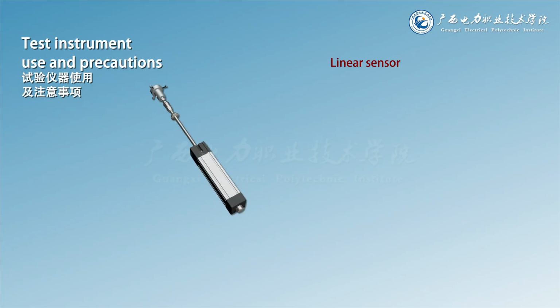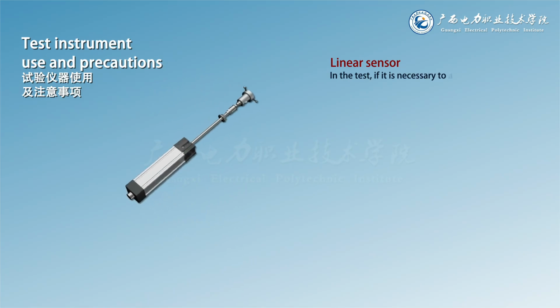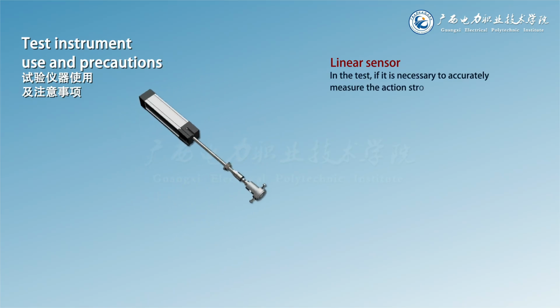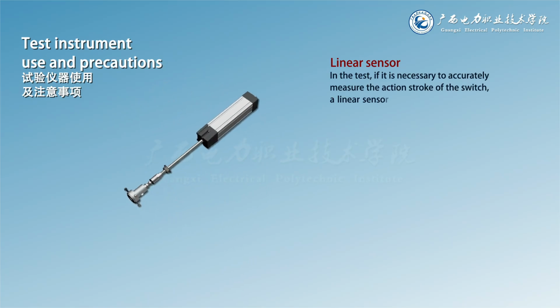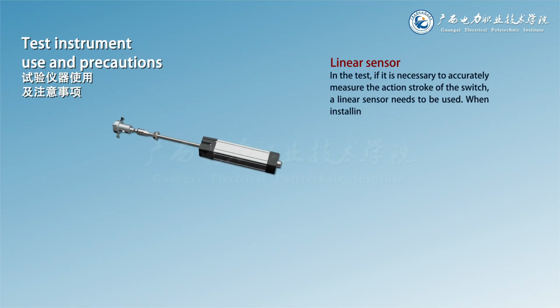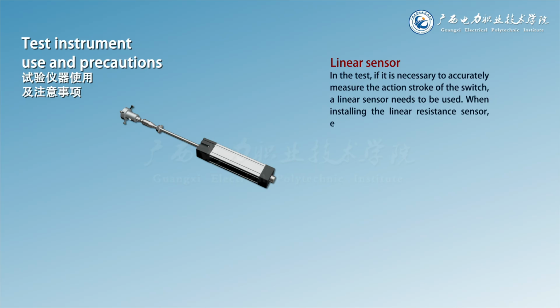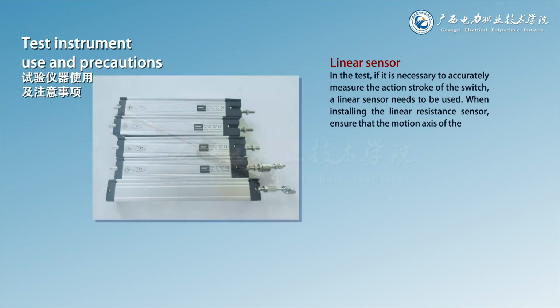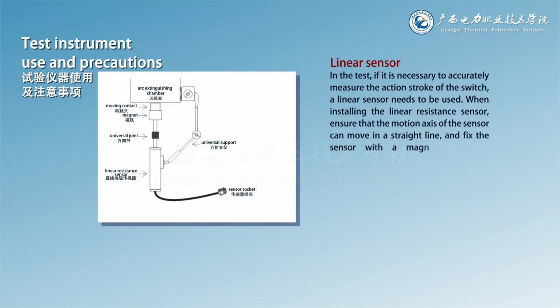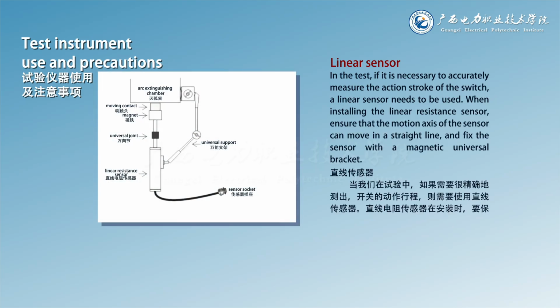Linear sensor. In the test, if it is necessary to accurately measure the action stroke of the switch, a linear sensor needs to be used. When installing the linear resistance sensor, ensure that the motion axis of the sensor can move in a straight line, and fix the sensor with a magnetic universal bracket.